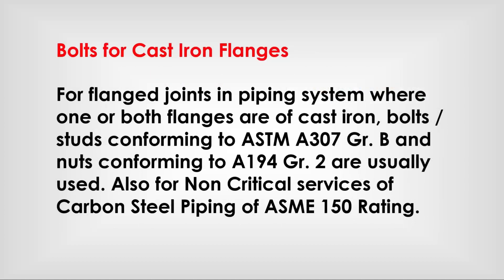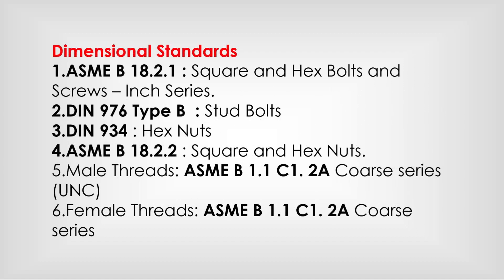For flange joints in piping systems where one or both flanges are of cast iron, bolts/studs conforming to ASTM A307 Grade B and nuts conforming to A194 Grade 2 are usually used. This also applies to non-critical services of carbon steel piping of ASME 150 rating. Dimension standards apply accordingly.